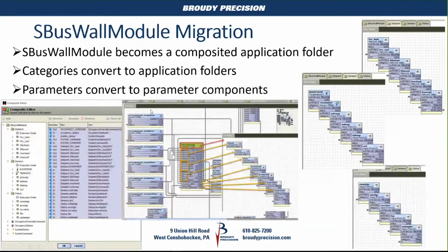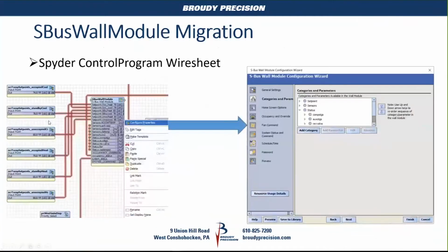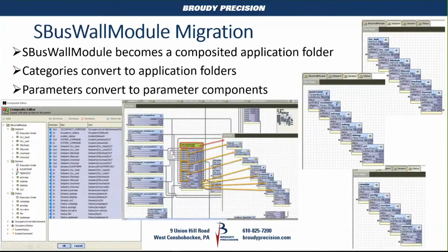So when this got migrated, if you notice, there's a nub, a connection on the fallback slot of these set points, which didn't exist in the Spyder. Since it's not a two-way street on this link anymore with how it works in a CIPer 30, if we go over here to the unoccupied cool set point, you'll see the nub on the output.